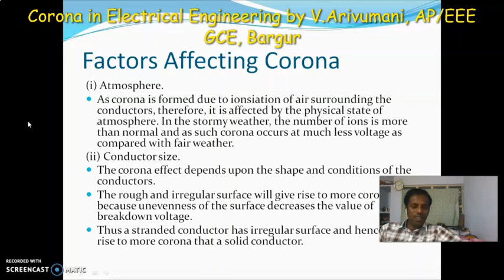The third one, spacing between conductors. If the spacing between conductors is lesser, the corona will occur easily. That's why we are making social distancing to prevent the coronavirus. If the spacing between the conductors is made very large as compared to the diameter, there may not be any corona effect. It is because larger distance between conductors reduces the electrostatic stresses at the conductor surface, thus avoiding corona formation. So it is another factor, distance.